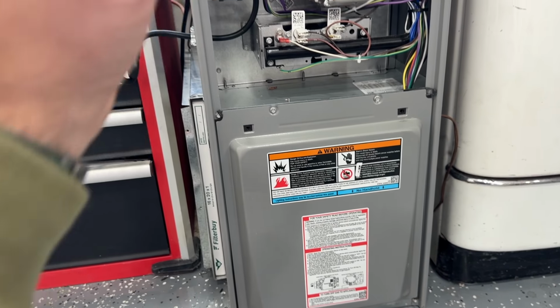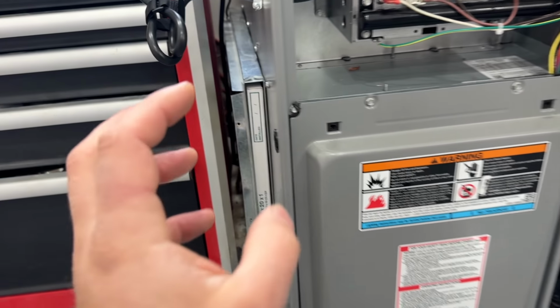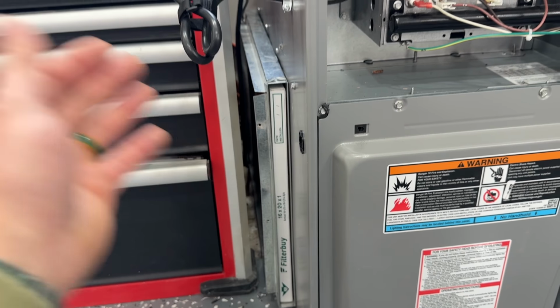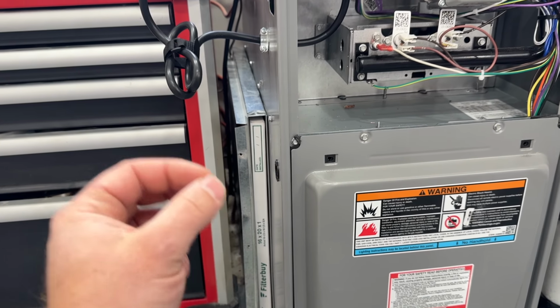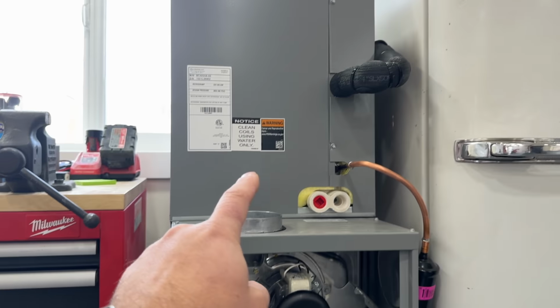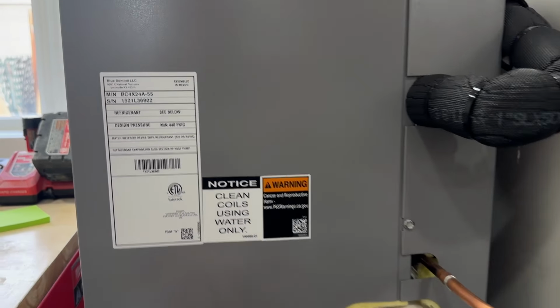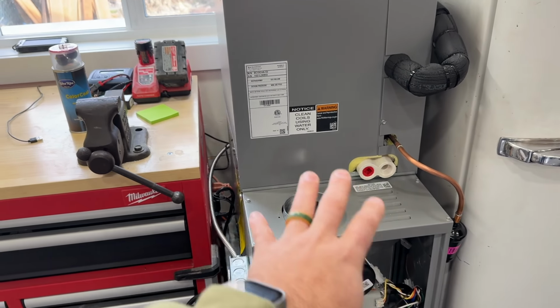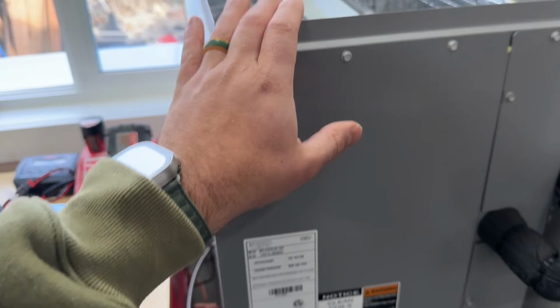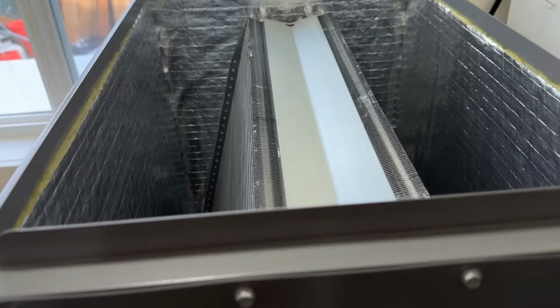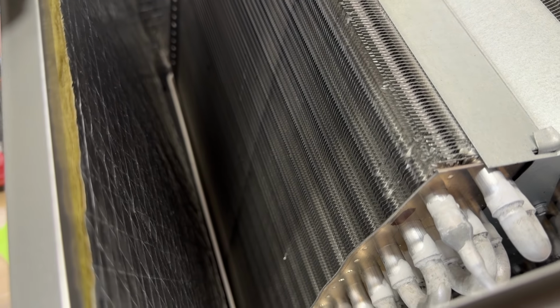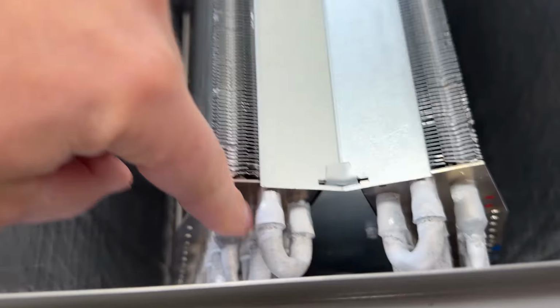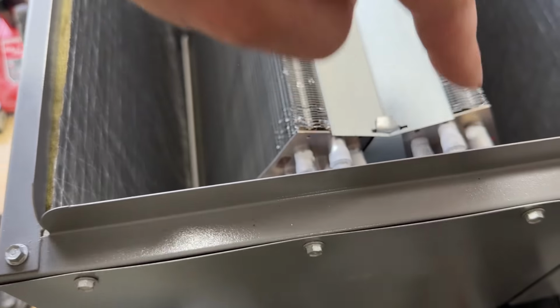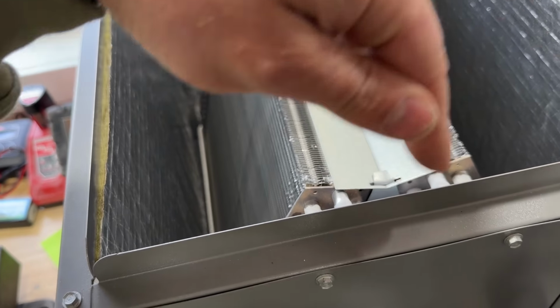Now, while we're on the topic of air filtration and airflow, something else that is critical is if you have had a dirty air filter for years and years, you could have very well clogged the coil. So I'm going to show you from the top here. This is obviously a demo furnace, so there are no safety hazards here. Obviously, you would see a vent and ductwork here in any other situation. But this is what the coil looks like. So typically it's going to be an A coil. As you can see, it's kind of shaped like an A. Sometimes they're shaped like an N.